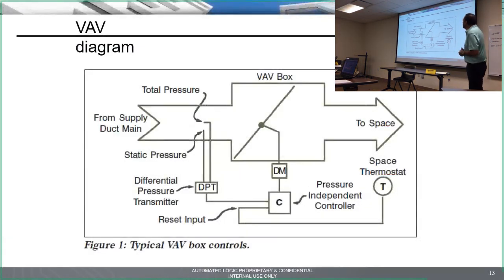So this is a drawing of a typical VAV box, right? And you guys have probably seen it, you've got a damper here. The damper is hooked up to a controller. The controller will modulate the damper to maintain the flow. So the number one thing that the VAV box does is it measures flow, measures a volume. And a lot of questions are, well, how does it do that? What's the magic behind it? How does it measure the flow?